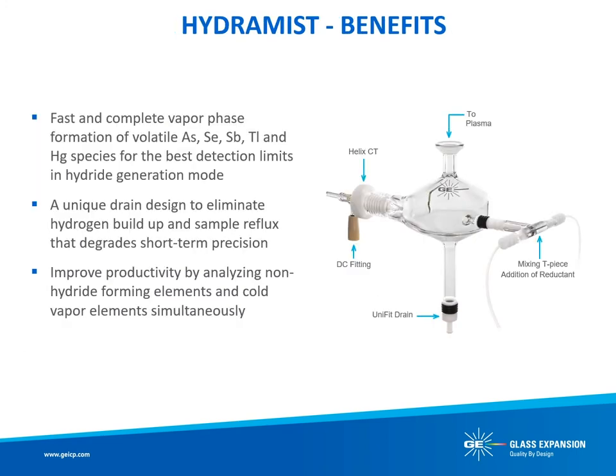For improved detection limits of arsenic, selenium, antimony, thallium, and mercury in environmental samples, cold vapor hydride generation is an alternative sample introduction method that can provide improvement in sensitivity for these elements. However, switching between a cold vapor and conventional pneumatic nebulization setup adds complexity and reduces laboratory productivity. In November of 2019, Glass Expansion introduced the Hydramist spray chamber, providing an accessory that allows for simultaneous multi-element analysis by conventional pneumatic nebulization and cold vapor hydride generation.